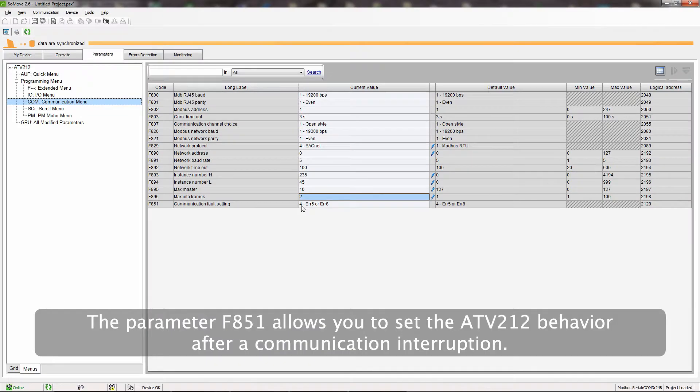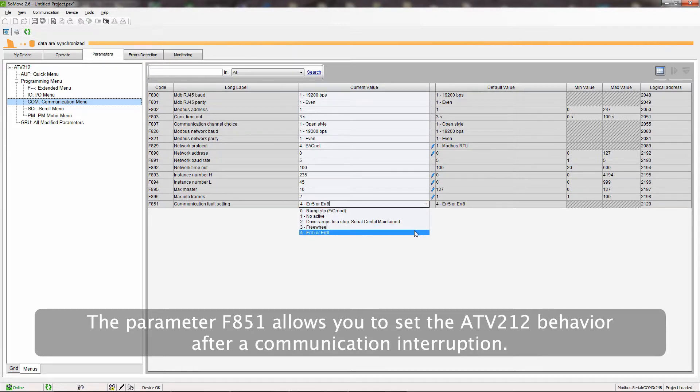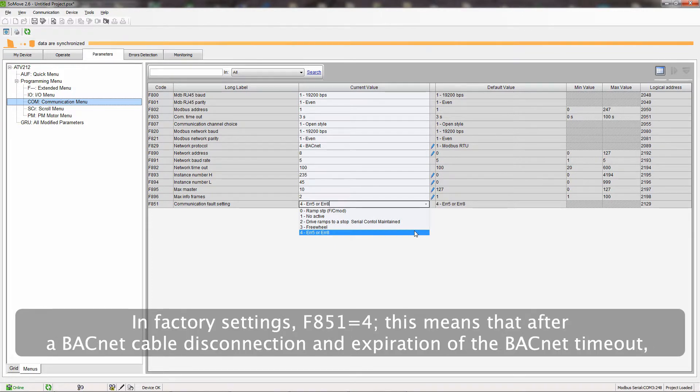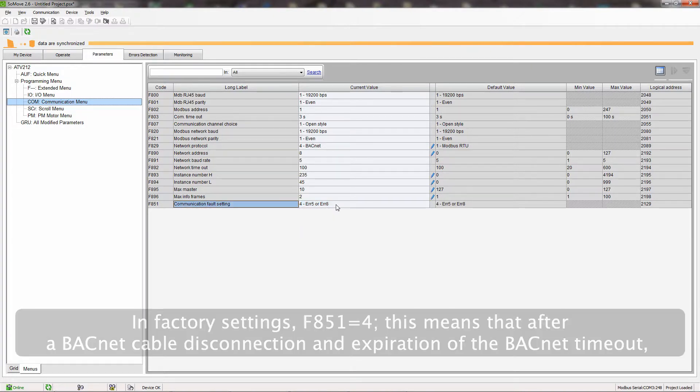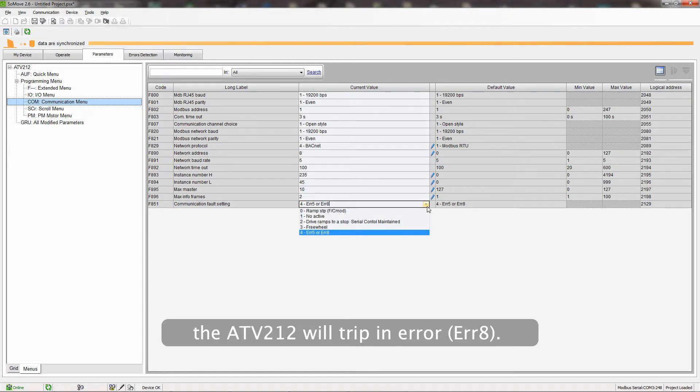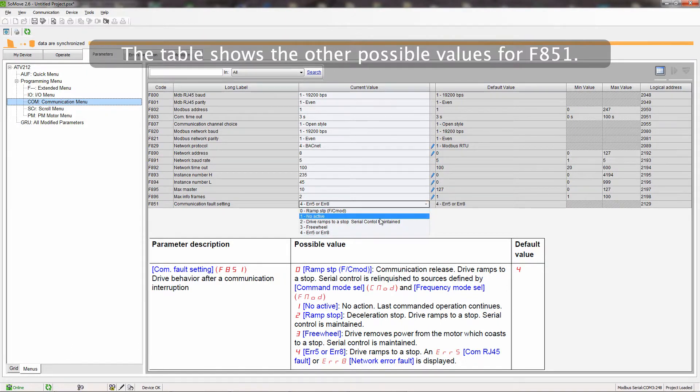The parameter F851 allows you to set the ATV212 behavior after a communication interruption. In factory settings, F851 equals 4. This means that after a BACnet cable disconnection and expiration of the BACnet timeout, the ATV212 will trip an error. The table shows the other possible values for F851.